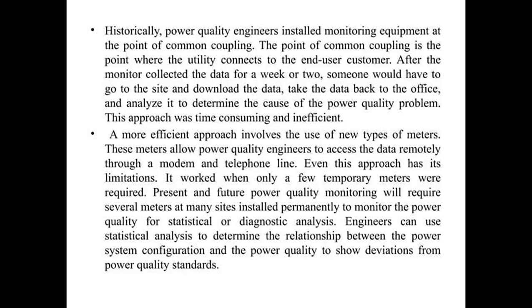These meters, what you can say, allow the power quality engineers to access the data remotely. This is very important. These meters work like a SCADA system, the supervisory control and data acquisition system. So you can check and take the data remotely, and by using that data you can determine what the power quality problem is. If you need to solve that problem, either we have to go to that site particularly, or remotely, whether we are going to solve it at the service level or at that particular level, and accordingly you have to take decisions and maintain the power quality.